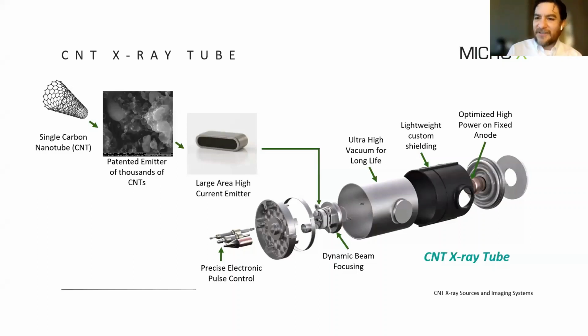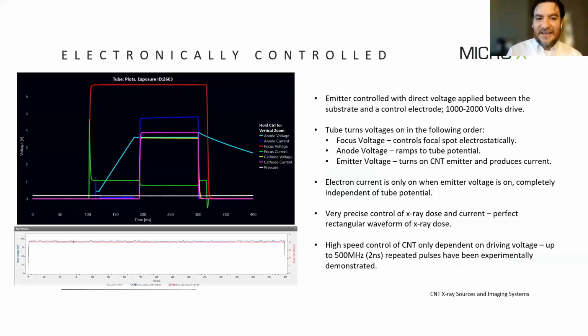So the first unique property of these carbon nanotube X-ray tubes is that they are electronically controlled. If we go back to the beginning and think about how typical X-rays are produced, you're running a current through a tungsten filament to generate thermionic emission. So there's a little bit of a lag in how precisely you can control the current and when, as you ramp the anode voltage, you begin to generate electrons. Alternatively, for our tube, first we turn on a focus voltage.